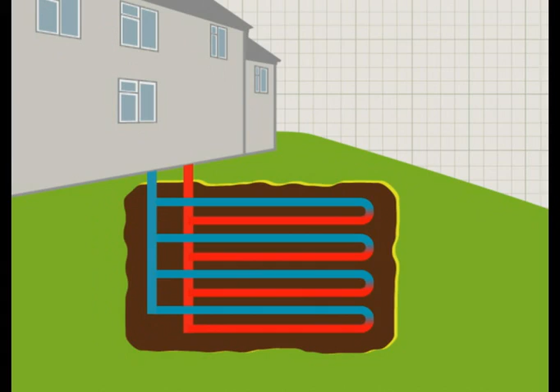Okay, well, let's have a look at some design options. There are three main options when it comes to installing a closed-loop ground source heat pump system. The first is vertically in a borehole, as a series of long U-shapes in well holes. Depending on energy needs, boreholes are usually 50 to 200 metres in depth. Alternatively, piping can be installed horizontally in a trench about 1 to 2 metres deep, or even a body of water. Trenches cost less than a borehole, but need more land area.